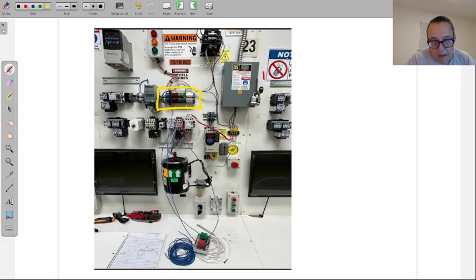So once I establish that L1 and L2 are providing power, if they don't, I work my way back. Hit the transformer, work my way back, hit the fuses inside of the disconnect. If there's no power at anything here, then we head north towards the panel. We keep working our way back until we hit the point where power has been lost. But assuming I have power on L1 and L2, that's the first thing I want to establish here.